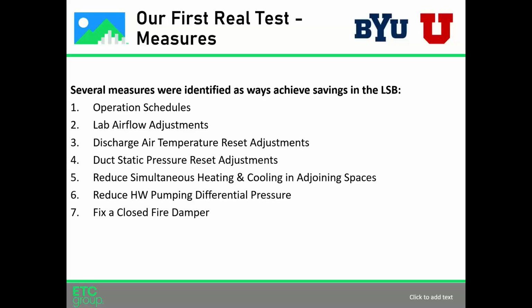We made significant changes to our discharge air and duct static pressure resets, and made those work together much better. We also had areas heating and cooling at the same time, with adjoining areas served by several VAV boxes, so we were able to coordinate those and reduce that simultaneous heating.